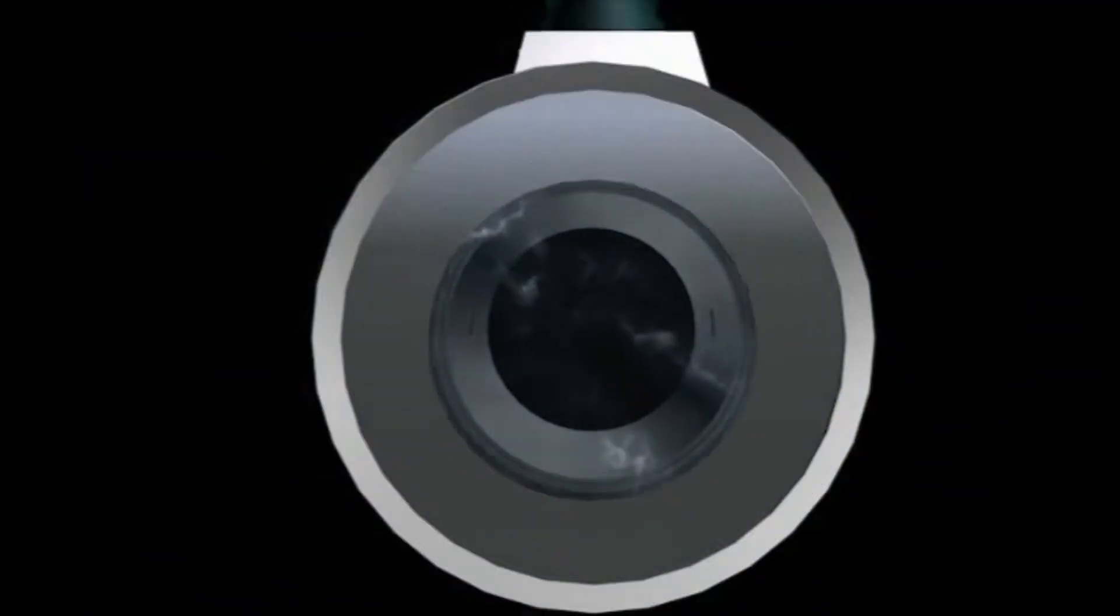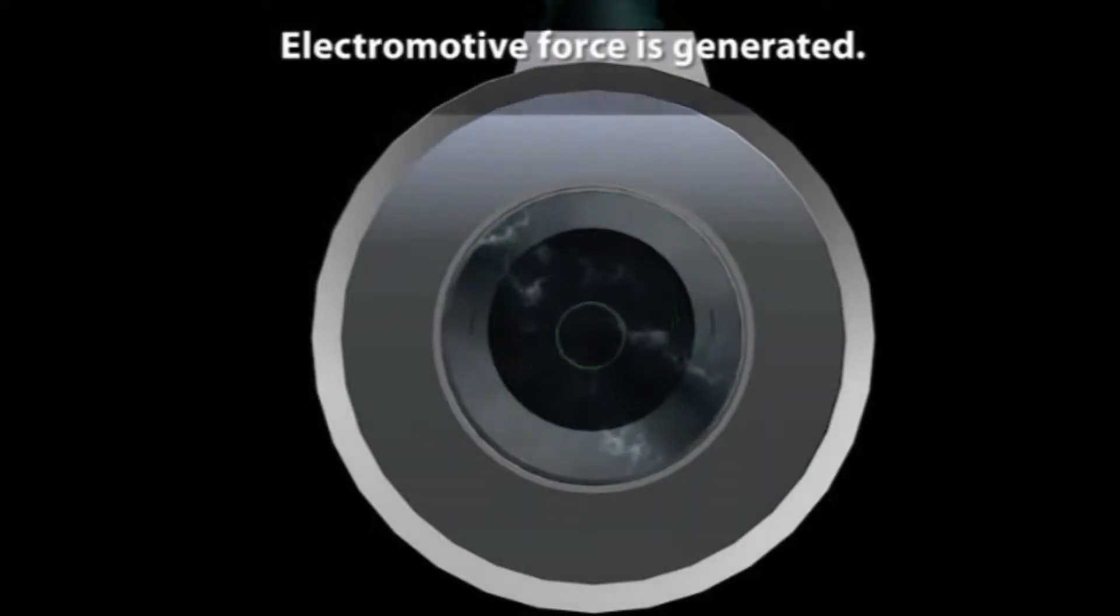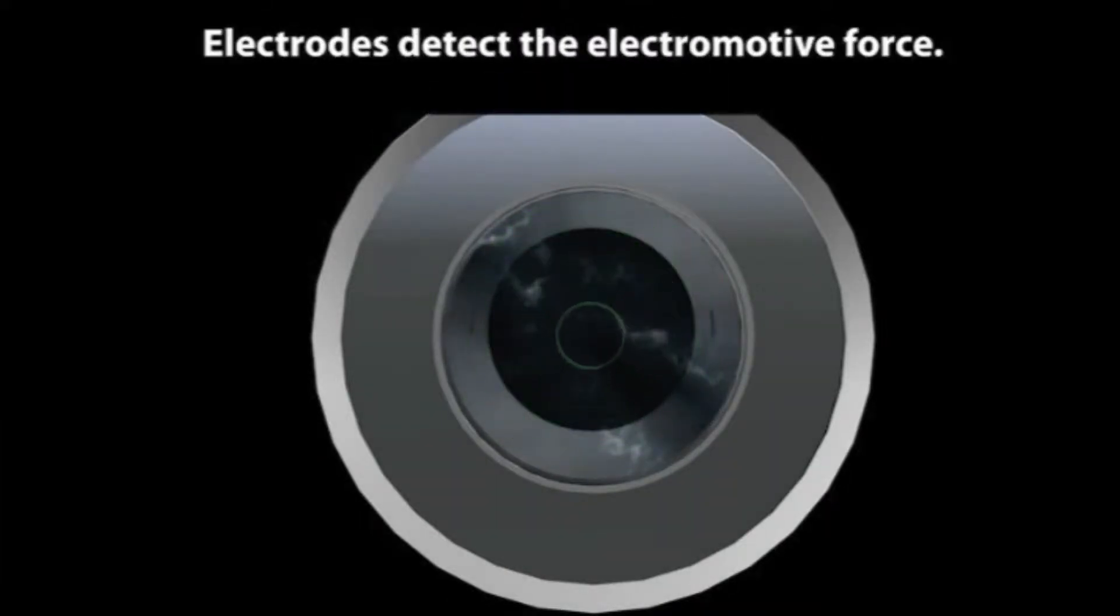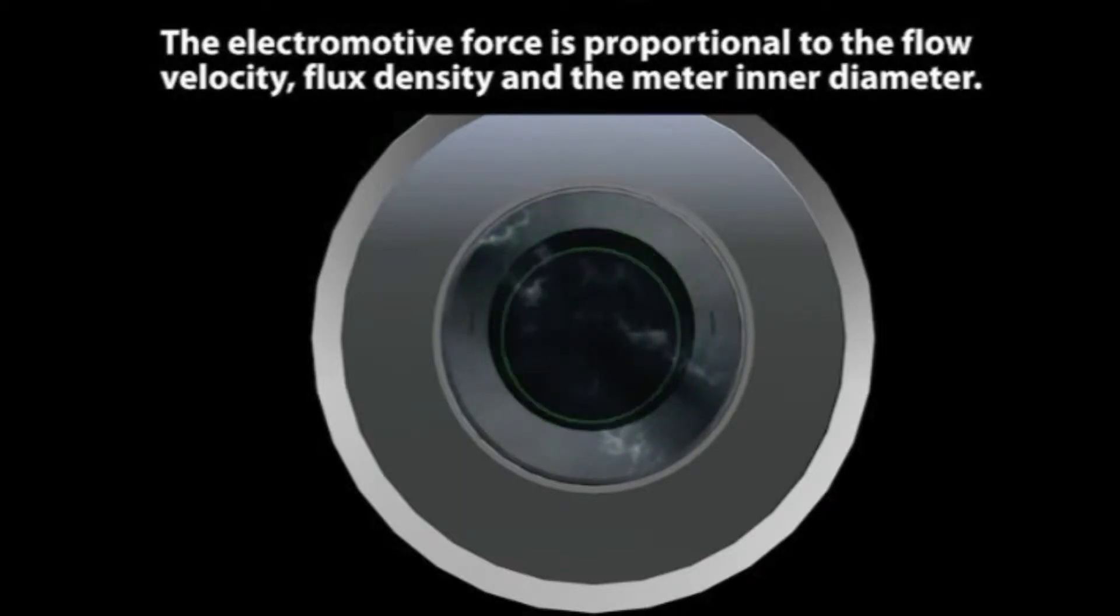As a conductive liquid flows through the flow tube, an electromotive force is generated. The electrodes detect the electromotive force. The electromotive force is proportional to the flow velocity, flux density, and the meter inner diameter.